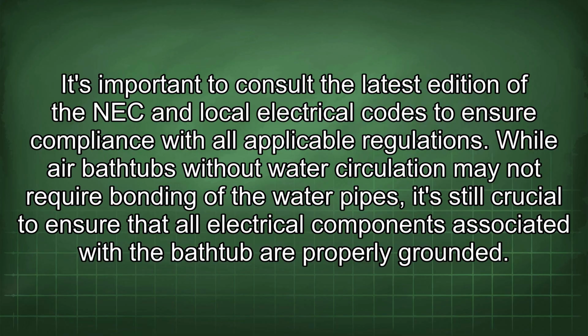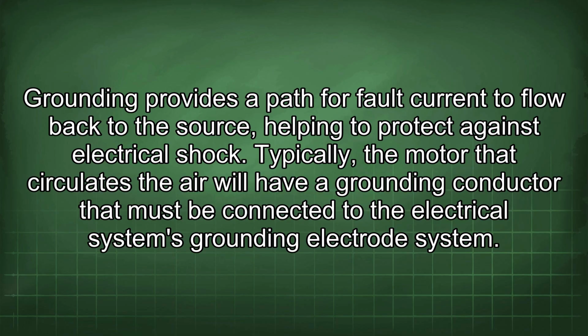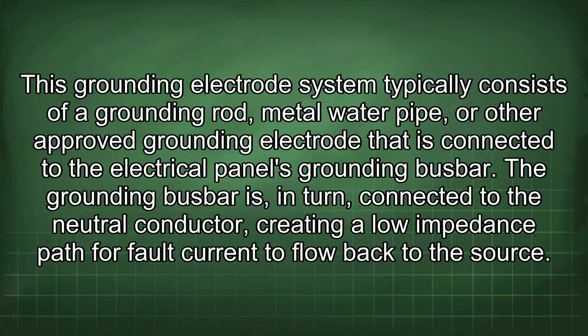While air bathtubs without water circulation may not require bonding of the water pipes, it's still crucial to ensure that all electrical components associated with the bathtub are properly grounded. Grounding provides a path for fault current to flow back to the source, helping to protect against electrical shock. Typically, the motor that circulates the air will have a grounding conductor that must be connected to the electrical system's grounding electrode system. This grounding electrode system typically consists of a grounding rod, metal water pipe, or other approved grounding electrode that is connected to the electrical panel's grounding busbar. The grounding busbar is, in turn, connected to the neutral conductor, creating a low impedance path for fault current to flow back to the source.